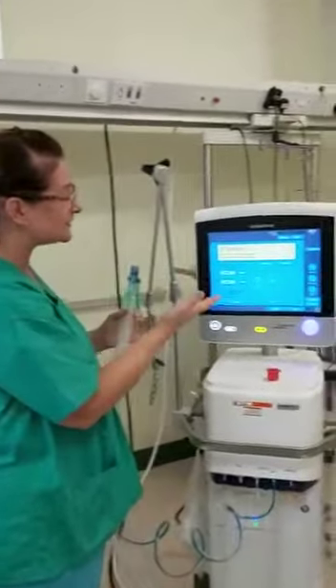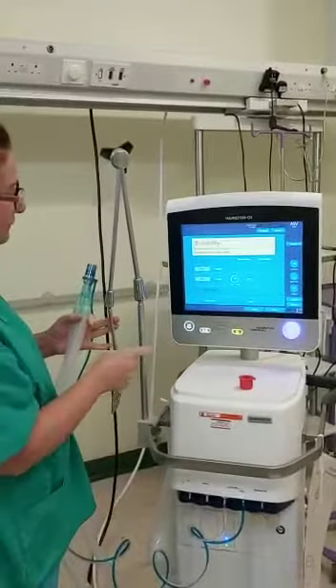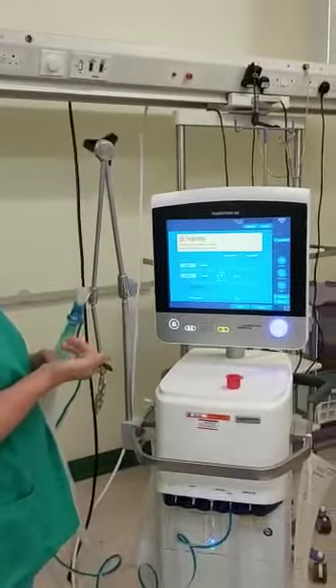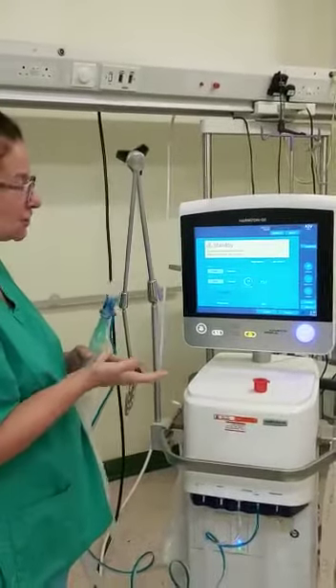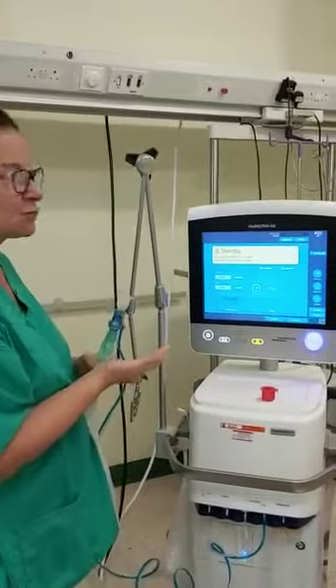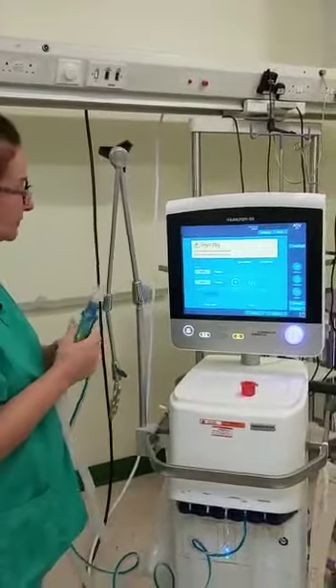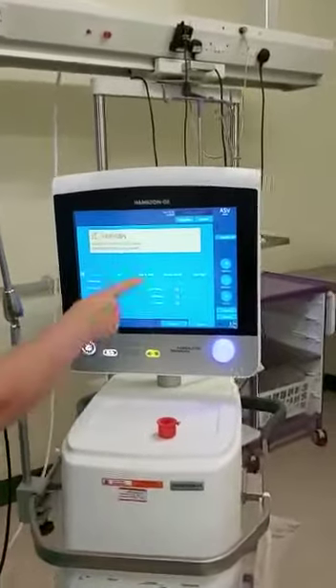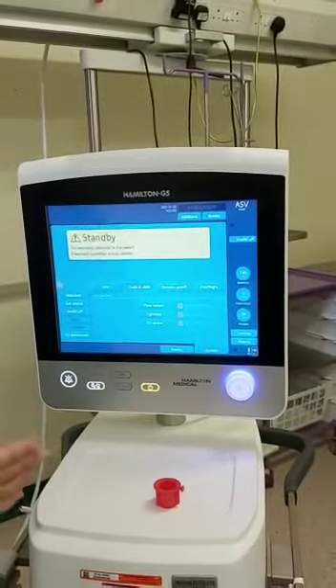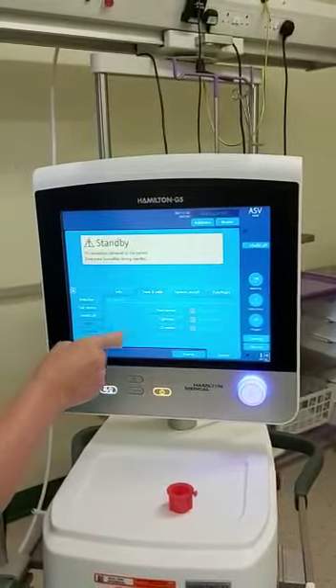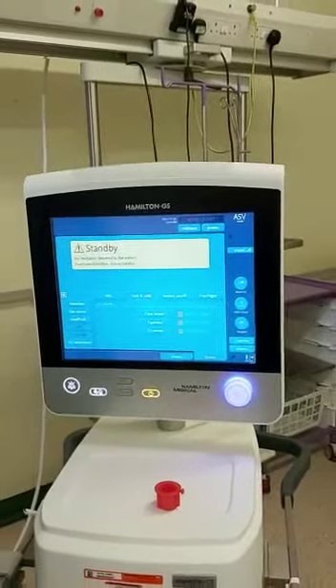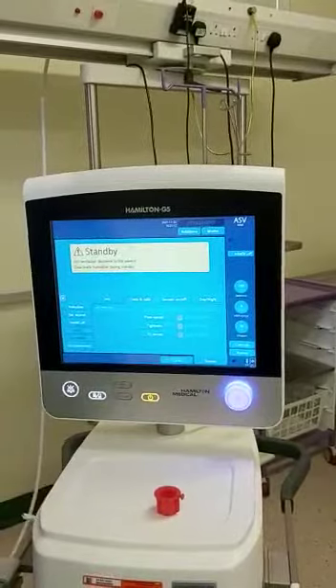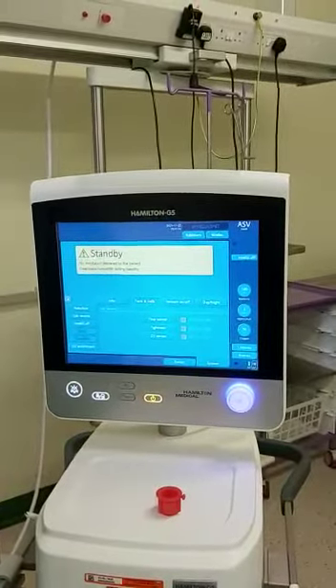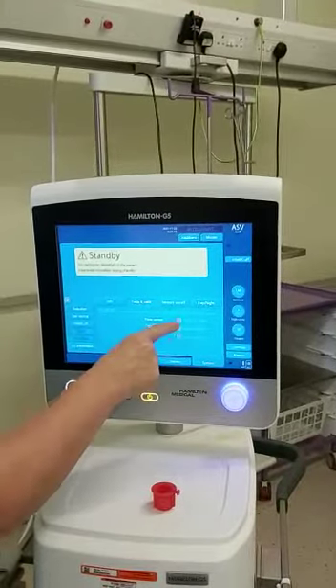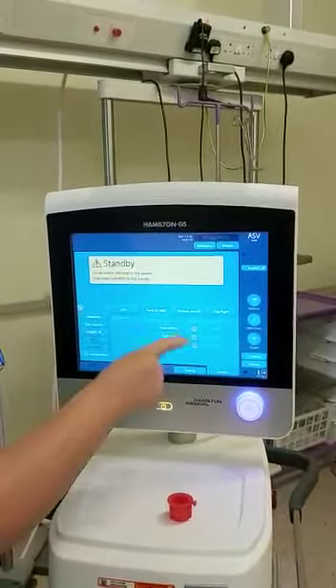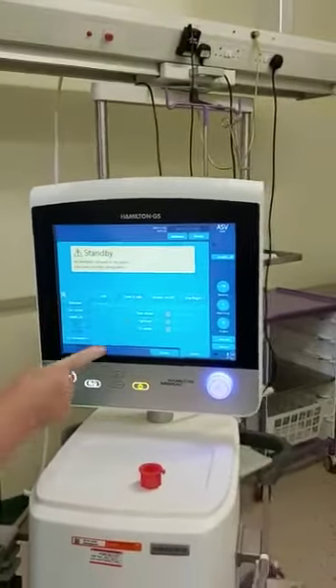Okay, once it's finished its self-test, you come to this home screen, and what we're going to do first is a pre-op check. This should always be done once the ventilator's been set up, ready following discharge of a patient or when a patient no longer needs it, and also prior to using the machine when we're getting an admission. So click on pre-op check, and it gives you three options, and in order to calibrate the machine you have to go through all three. So you've got flow sensor, tightness and oxygen sensor. For the flow sensor and the tightness, the machine will ask you and direct you to do certain things, but the oxygen sensor, it does itself once you've clicked on that button. Once it's completed, you get a green tick to say that it's successful, and it will show the date and time when that was done. So we're going to do the flow sensor first.